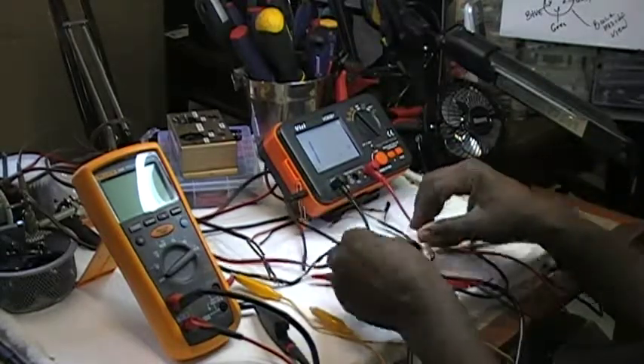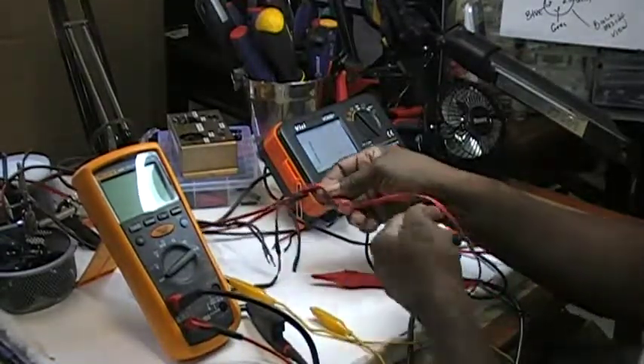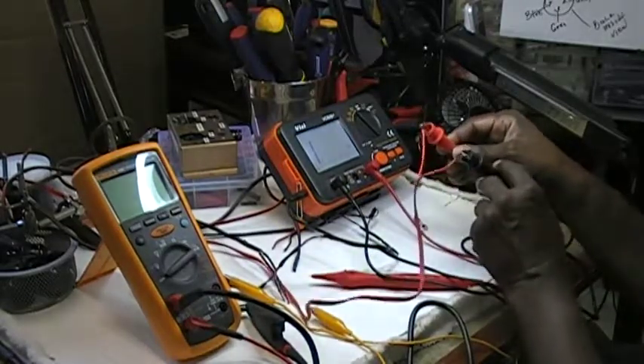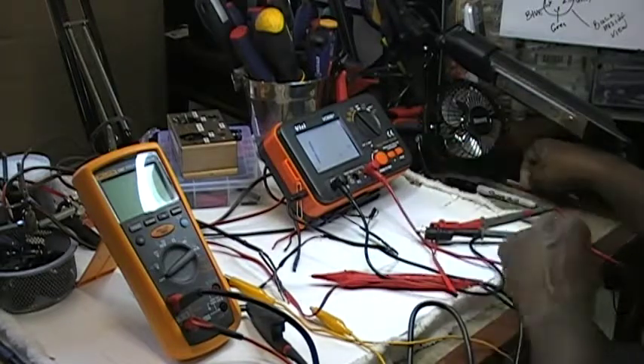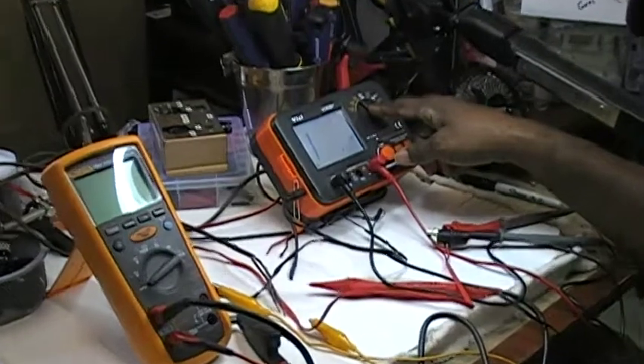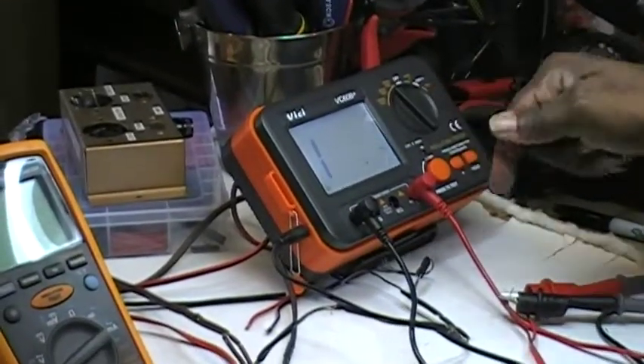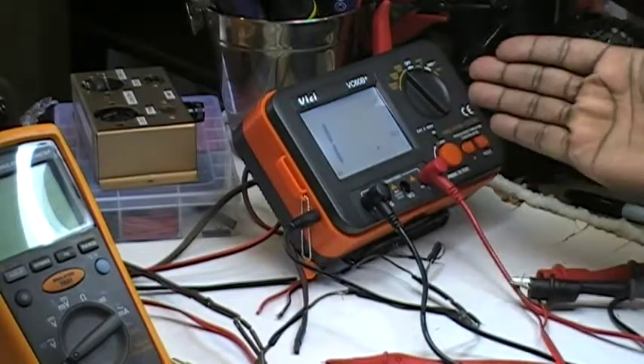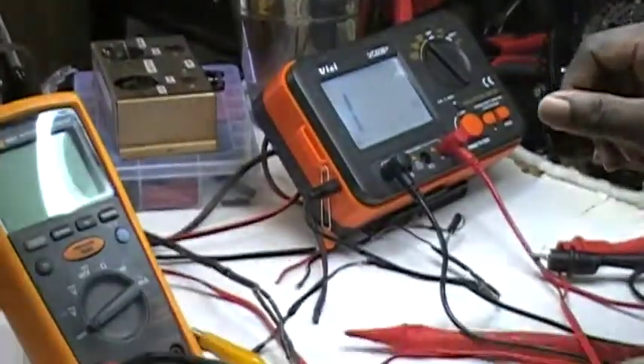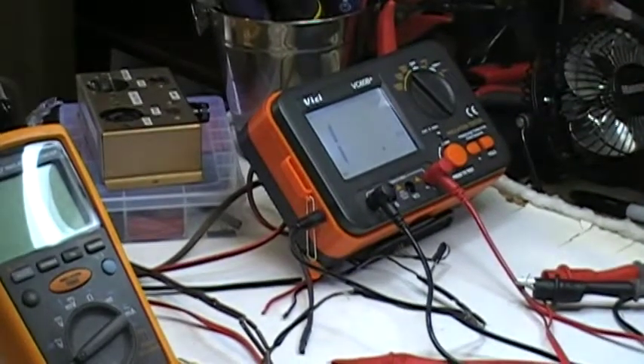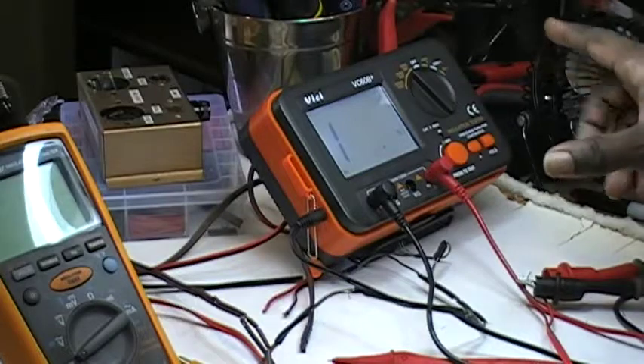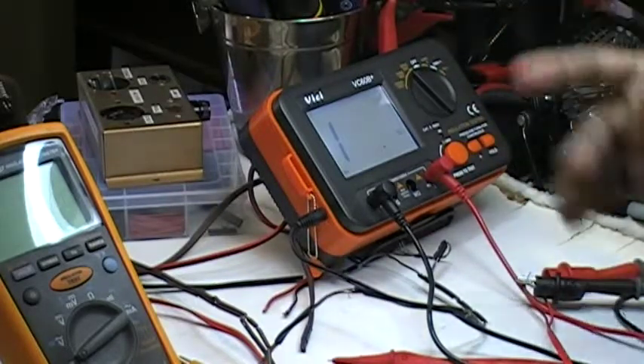Let's start with a control wire. This wire I know is good, a new cable, connected to the alligator clips. I have it set at 200 volts because we're going to run voltage through that line and look at the resistance measured while running voltage through it. Anything above 1 megaohm is considered good; below 1 megaohm is bad.